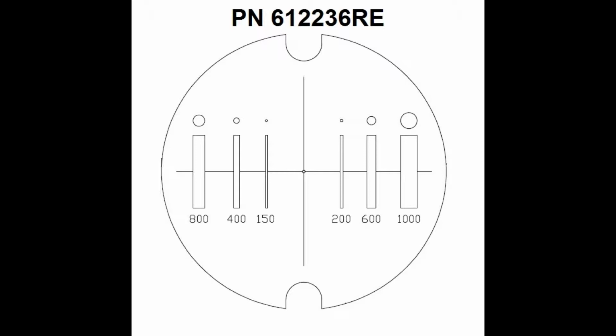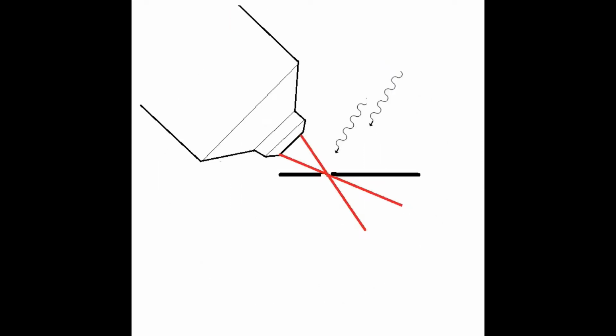This slotted sample is used to determine the precise location of the analyzer's focal point by moving the sample stage and determining where the silver XPS signal is and where it drops off as the sample is moved to where the analyzer is looking into a slit. By comparing the microscope image on the TV monitor to the analyzer signal, you can determine the precise analyzer focal point. The analyzer lens design accommodates a number of different areas that are determined by changing the analyzer aperture knob and also the aperture setting in the software.